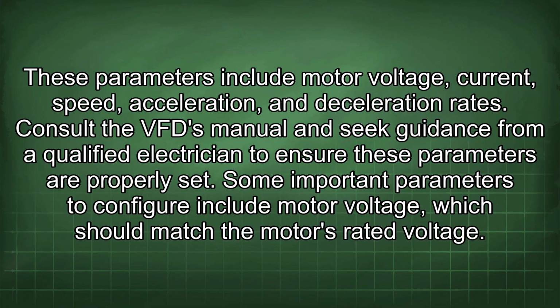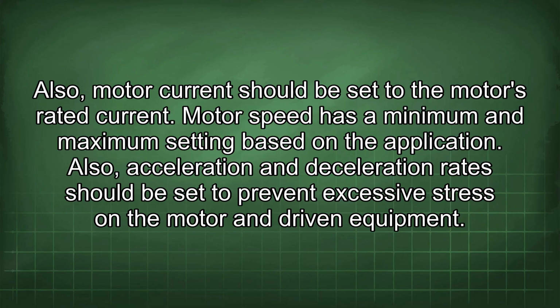Some important parameters to configure include motor voltage, which should match the motor's rated voltage. Also, motor current should be set to the motor's rated current. Motor speed has a minimum and maximum setting based on the application. Also, acceleration and deceleration rates should be set to prevent excessive stress on the motor and driven equipment.